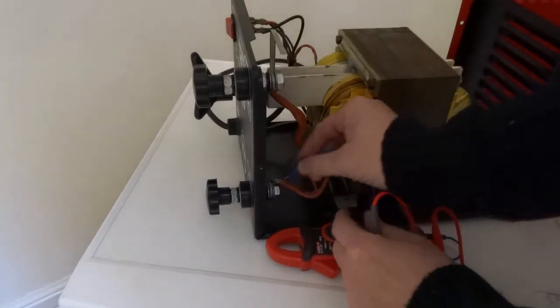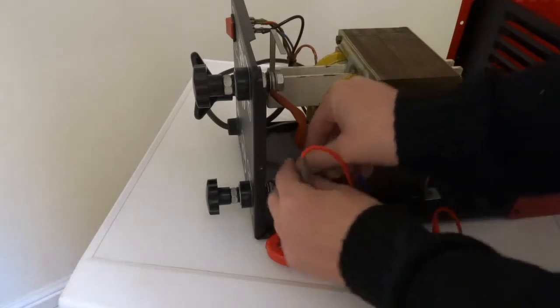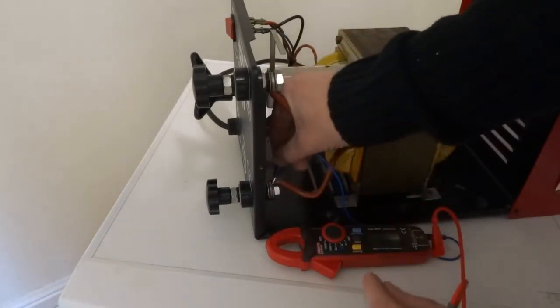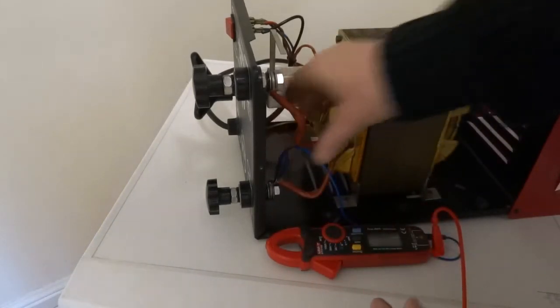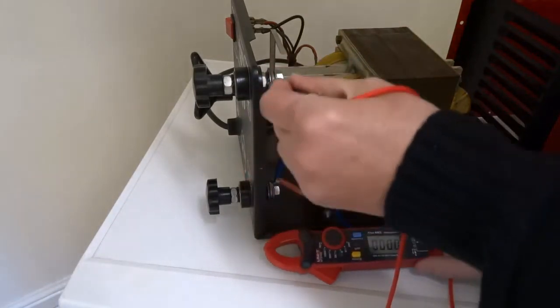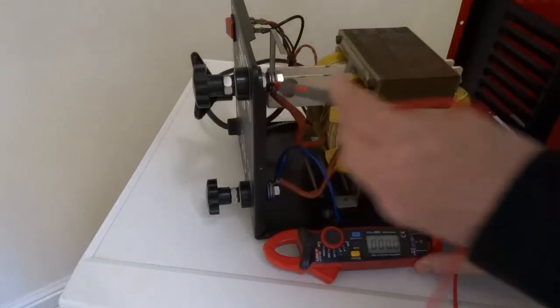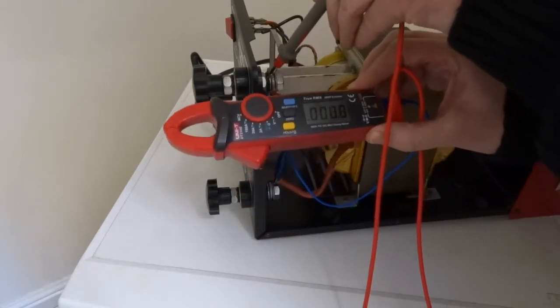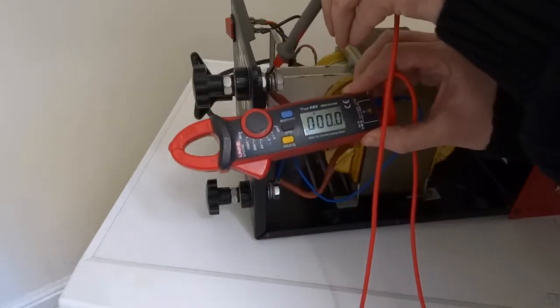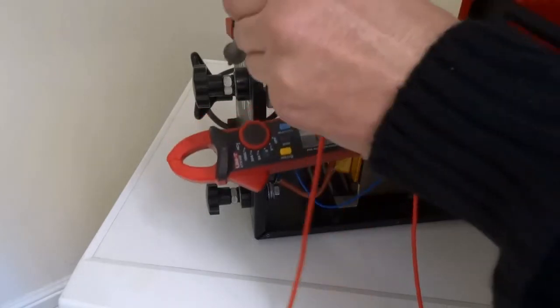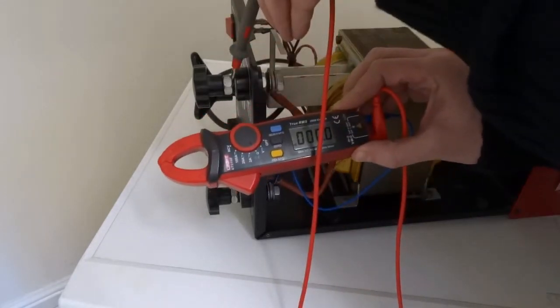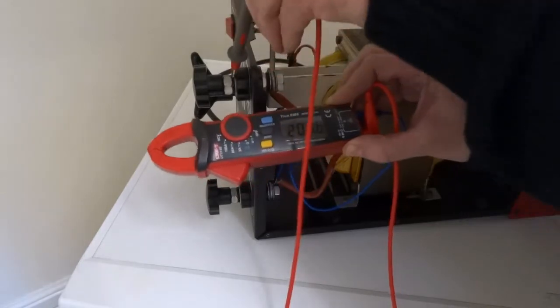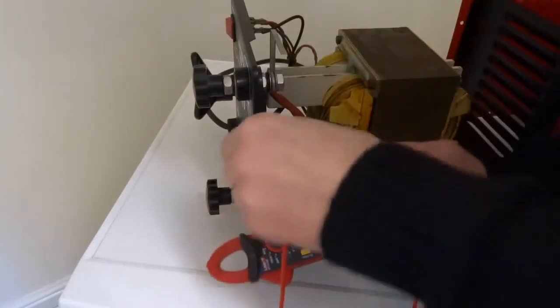I've just connected this side to one side of it, and I'm going to test the other side. There you go, really low ohms, even lower than before - there's a thicker wire. And then I'm going to test this side as well to make sure it's the same, so I'm testing the connections as well in between there, and I'll do the same down here.